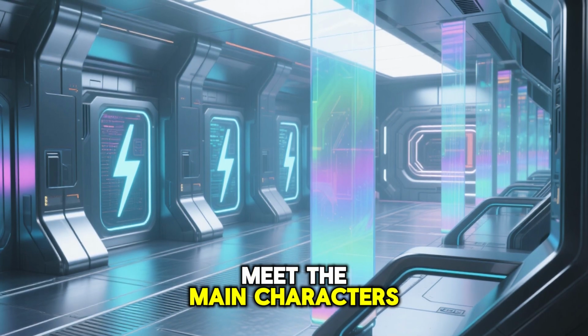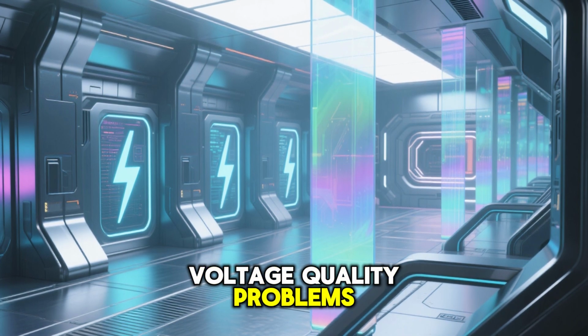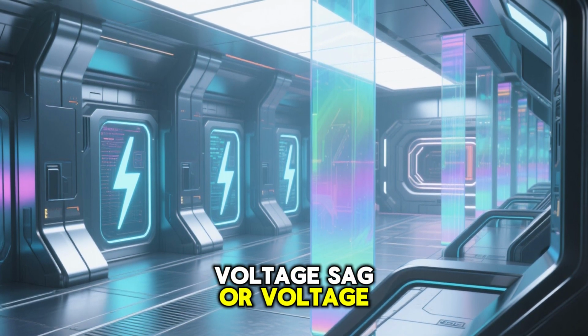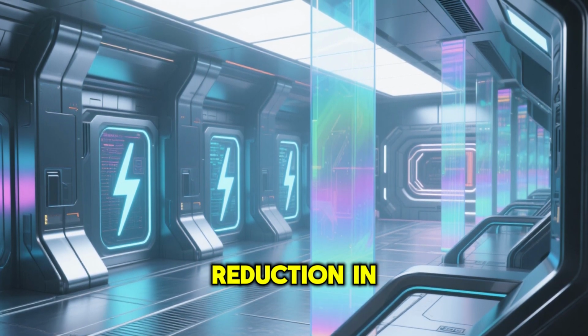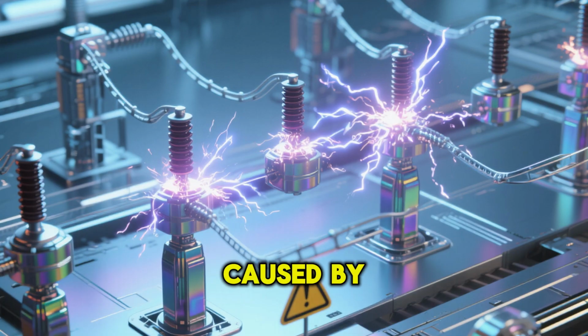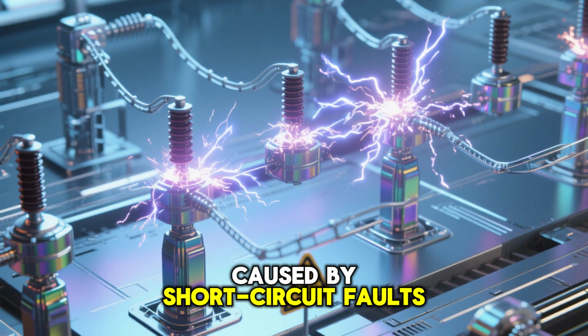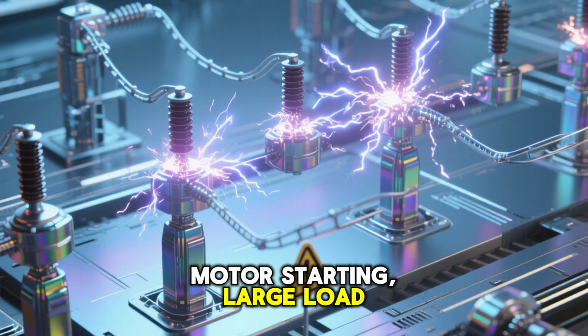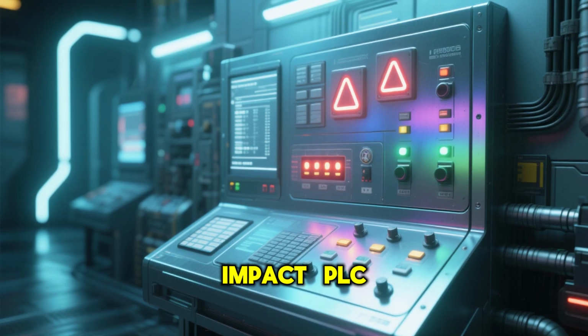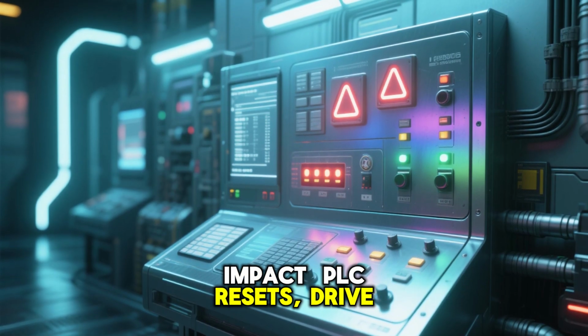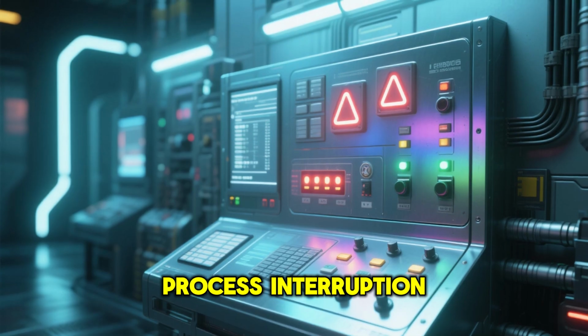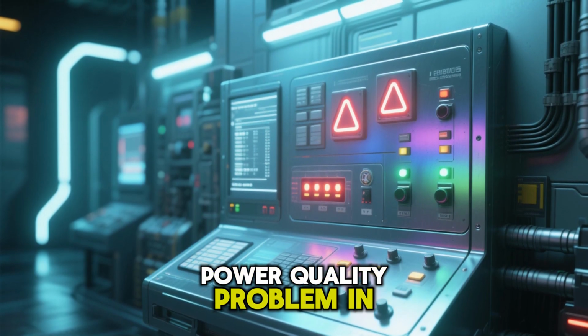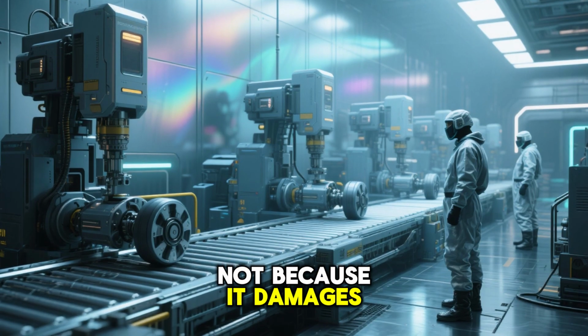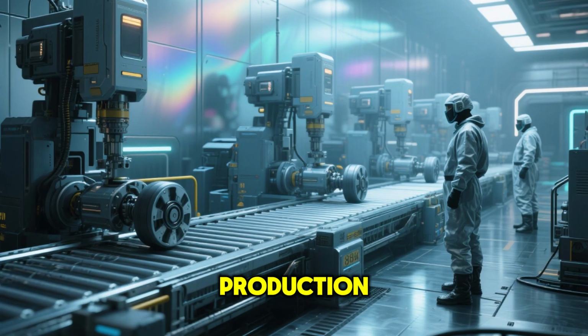Meet the main characters. Types of voltage quality problems. Voltage sag or voltage dip. A short reduction in voltage magnitude caused by short circuit faults, motor starting, large load connection. Impact: PLC resets, drive trips, process interruption. This is the most expensive power quality problem in industry, not because it damages equipment, but because it stops production.